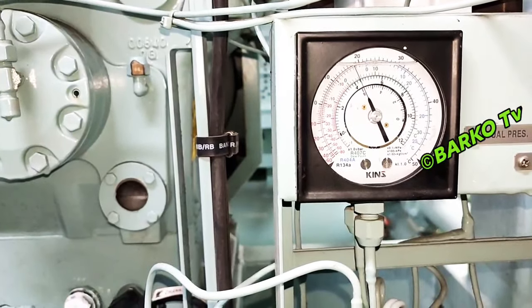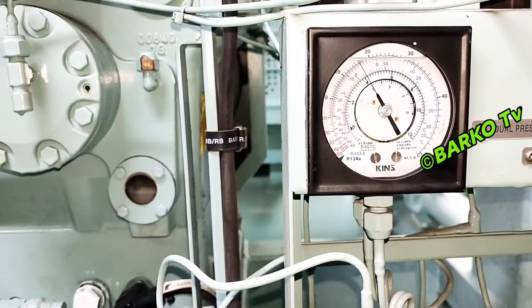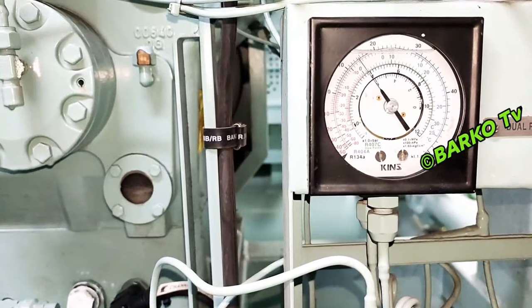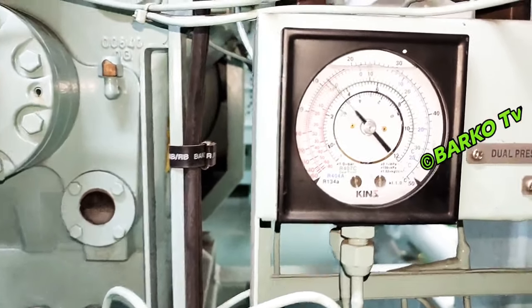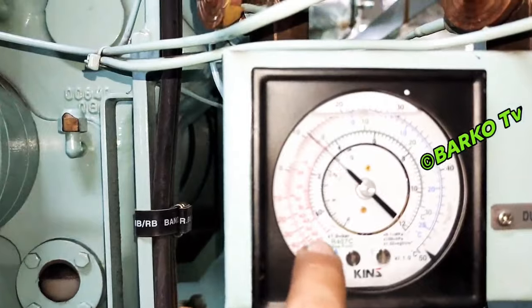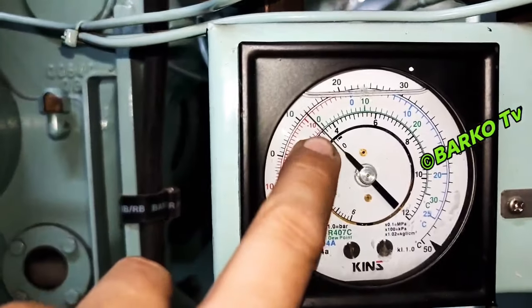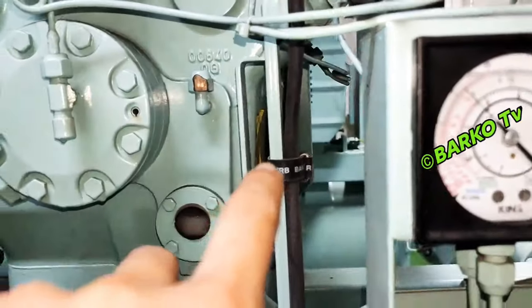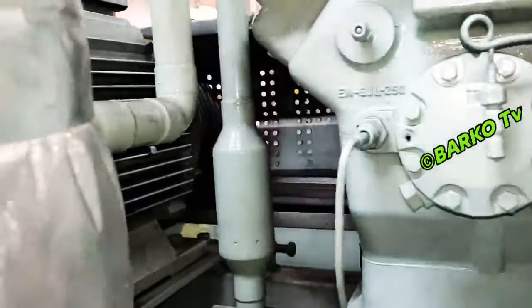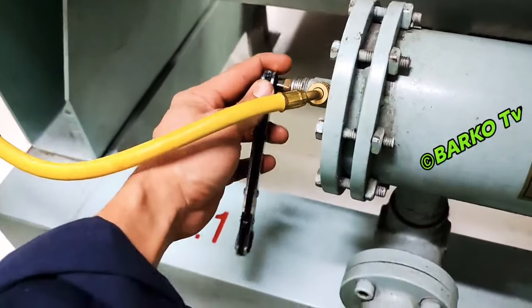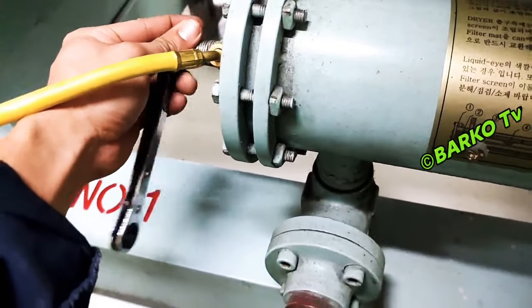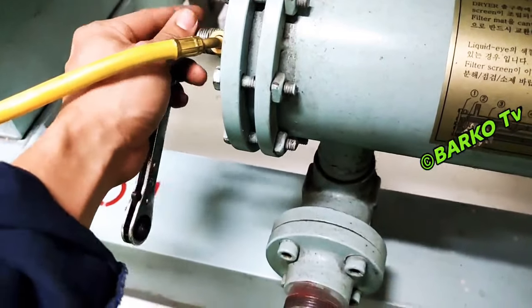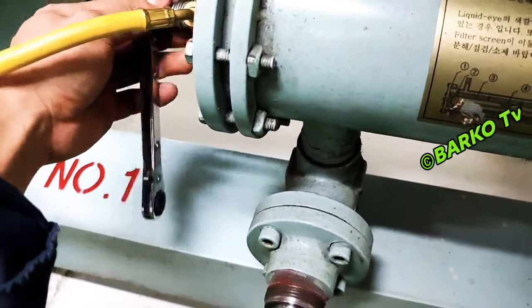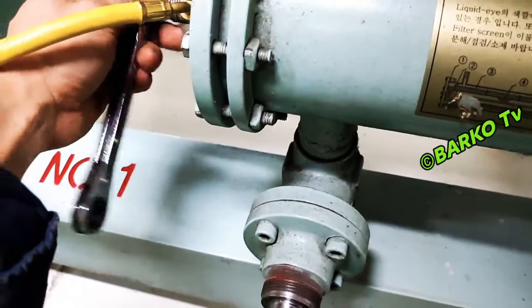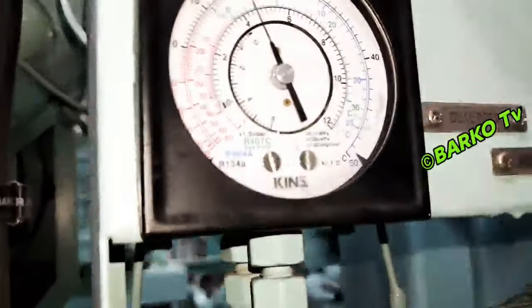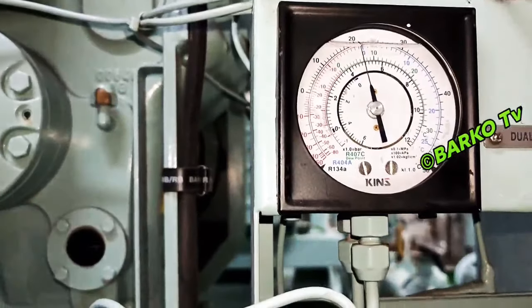Right now our compressor is still running, and then almost triggered. Okay, low suction triggered and the compressor stops. Next step, you open the liquid charging valve. This line, the yellow line, is already pressured up because our liquid valve at the bottle is already open. Right now the pressure is starting to rise up.